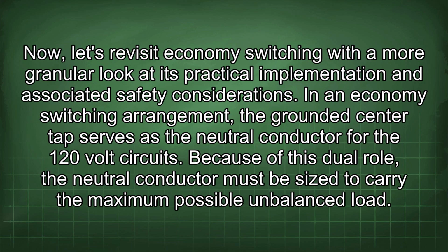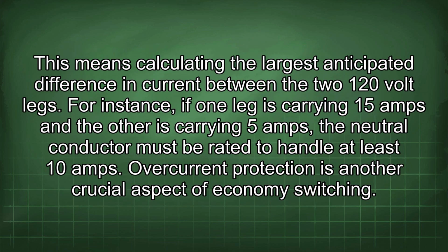Now let's revisit economy switching with a more granular look at its practical implementation and associated safety considerations. In an economy switching arrangement, the grounded center tap serves as the neutral conductor for the 120 volt circuits. Because of this dual role, the neutral conductor must be sized to carry the maximum possible unbalanced load. This means calculating the largest anticipated difference in current between the two 120 volt legs. For instance, if one leg is carrying 15 amps and the other is carrying 5 amps, the neutral conductor must be rated to handle at least 10 amps.